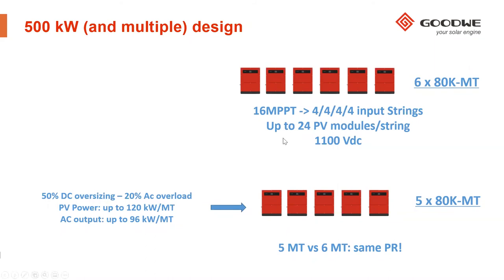And on top of that, you can use up to 24 PV modules per string with an input of 1100 volt DC. This is our classical proposal for the 500 kilowatt project and for multiples of this project. So you see a limited number of devices, just 6.